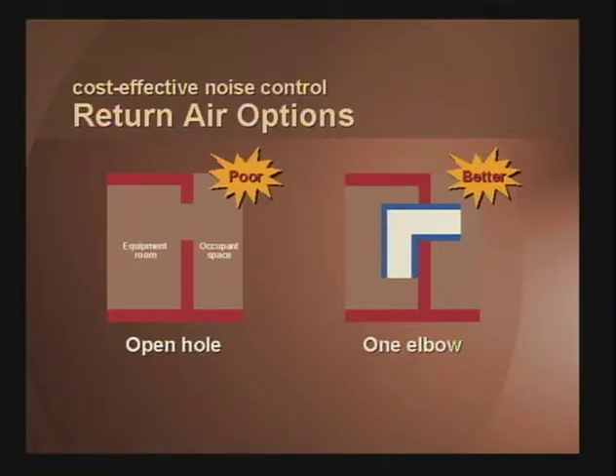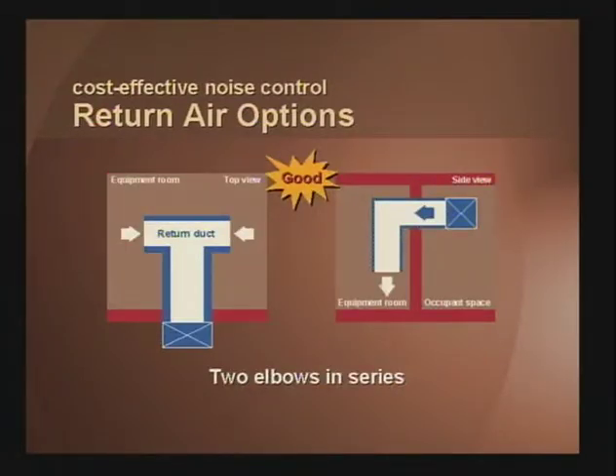The next level up would be a 90-degree elbow with two of them. Basically, a 90-degree elbow in the mechanical room followed by a T out over the occupied space. If one elbow is good, two is better. When you split the duct, try to make those legs about 4 to 5 feet out to disperse the noise over a wider area and thus get better performance out of this device. Remember, keep your velocities under 1,000 feet per minute.